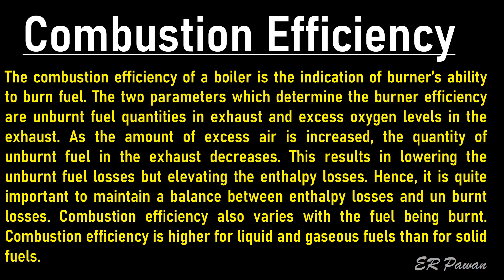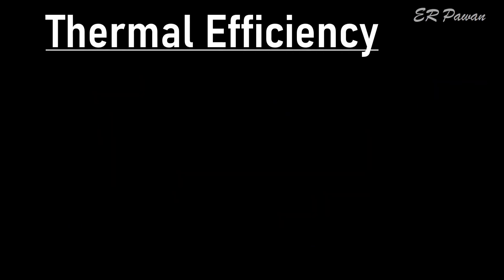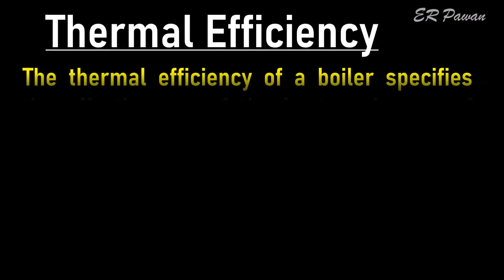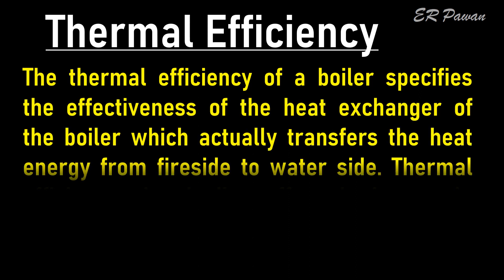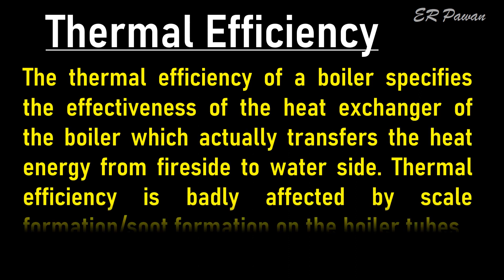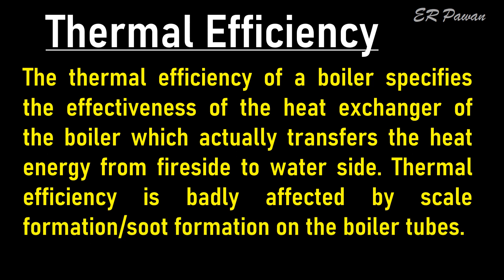Combustion efficiency also varies with the fuel being burnt. Combustion efficiency is higher for liquid and gaseous fuels than for solid fuel. Thermal efficiency: The thermal efficiency of a boiler specifies the effectiveness of the heat exchanger of the boiler which transfers heat energy from the fire side to the water side. Thermal efficiency is badly affected by scale formation or soot formation on the boiler tubes.